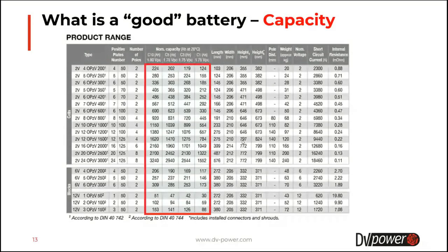Those parameters ultimately affect the capacity reduction. An important thing to say here is that it is crucial to perform the same test every time when testing the battery. When you install the battery, if you perform a C5 test, every time after that you have to perform a C5 test, and that way you will have a trend of your battery, and it will be easy to notice when the battery capacity is starting to decrease. When the battery capacity starts to decrease more quickly than before, you can take notice and be prepared for its end of life in a year or two, and you have to buy a new battery to overcome that problem.